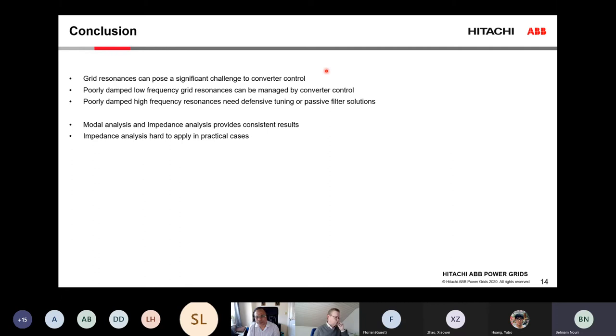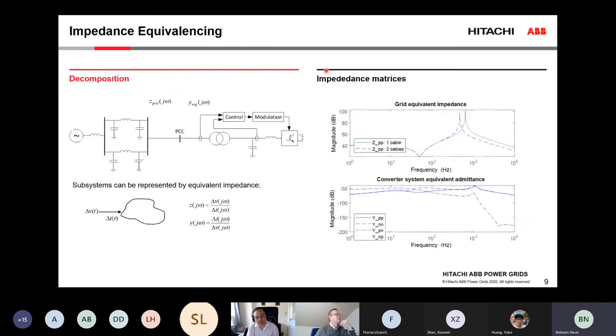Actually, I'm wondering if there is somehow inspected the validation of the models, for example, either the impedance-based models or the eigenvalues. What would be the challenges for the validation of such models? Yeah. So, I basically hear that we are talking about these impedance matrices here, and there are different ways of getting to those. So one is for the grid side, we often use models. So we know the topology of the grid. We have, say, either detailed or approximate information about the frequency dependency of the parameters here, so it is usually quite straightforward to calculate at least a frequency dependent model of the grid. How accurate that is, of course, is another issue.